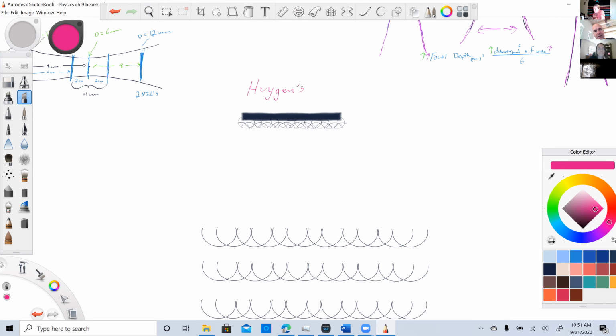What he discovered is that if the aperture, which is the width of the element, is considerably more than the wavelength, then the element acts as if it's thousands, if not millions, of individual elements, all pulsing sound at the same time. So it doesn't act like a single sound source, it acts like many sound sources.